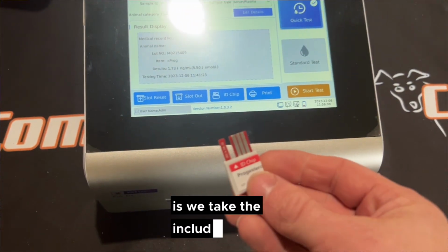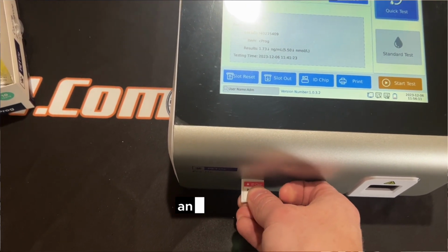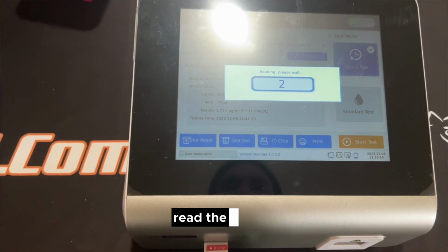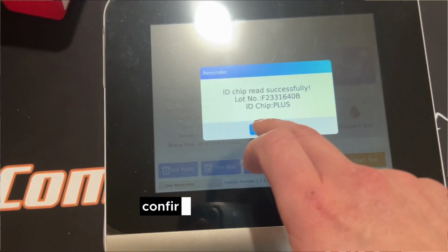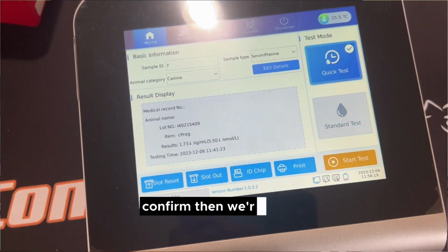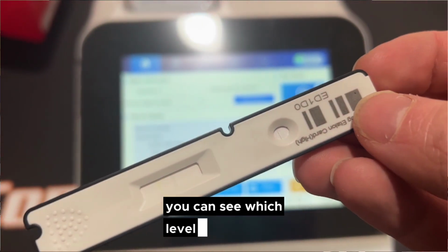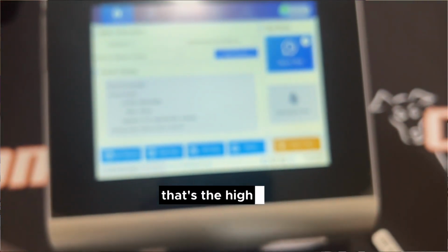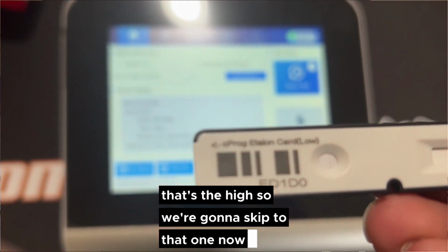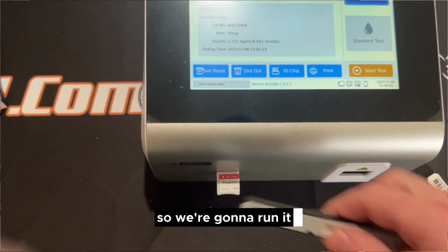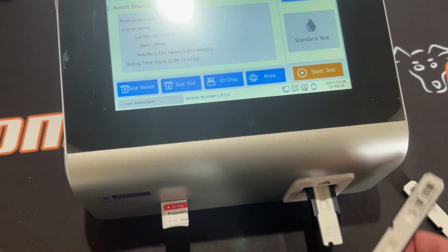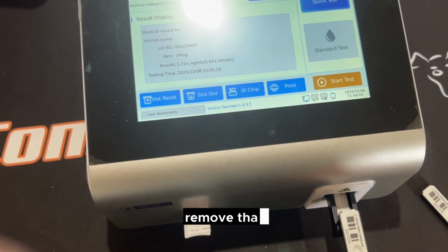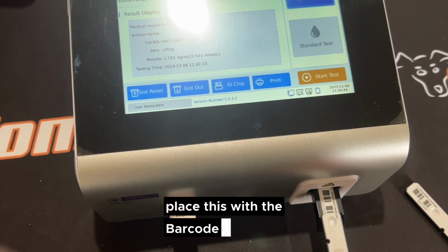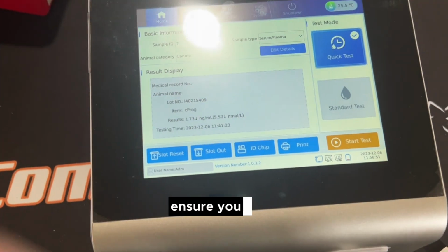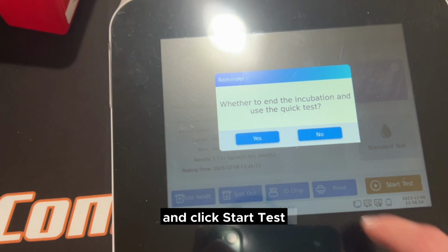So what we do is we take the included ID chip, insert it into the machine, read the ID chip, confirm. Then we're going to take the low level first. You can see which level it is based on the writing on each one. That's the high, so we're going to skip to that one. Now this is the low, so we're going to run it. First we'll put the slot out, remove that, place this with the barcode in first. You want to ensure you're on quick test and click start test.